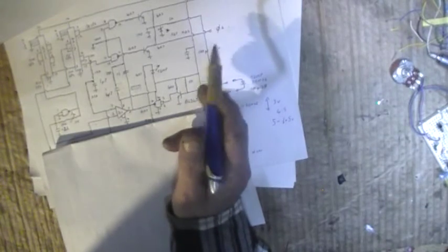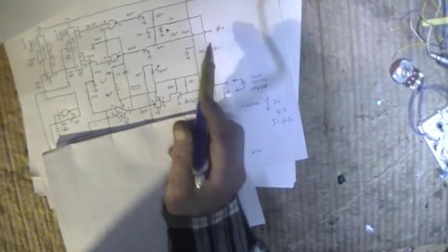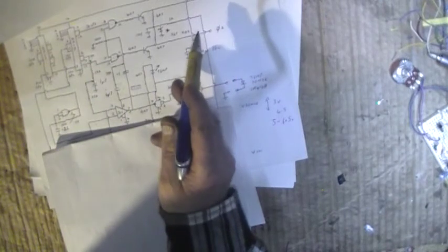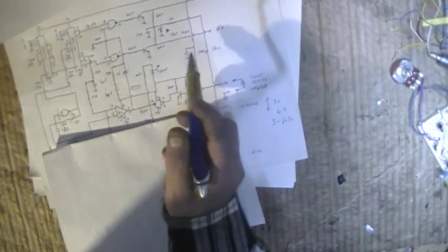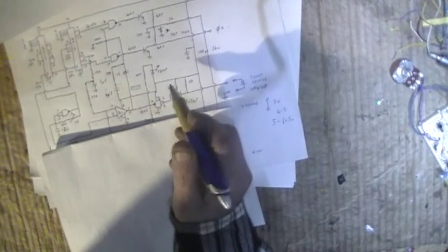And this is great, but how do we start it again? Well, again, a bit of cleverness comes to the rescue. We simply have a power on reset. So to reset the inverter, all we're going to do is turn the power off, remove the overload, of course, turn the inverter off, wait a few seconds, turn it back on.